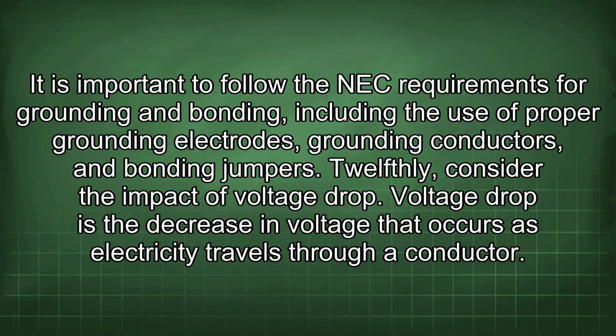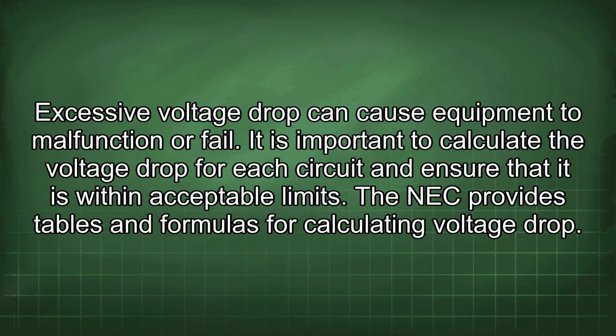12thly, consider the impact of voltage drop. Voltage drop is the decrease in voltage that occurs as electricity travels through a conductor. Excessive voltage drop can cause equipment to malfunction or fail. It is important to calculate the voltage drop for each circuit and ensure that it is within acceptable limits. The NEC provides tables and formulas for calculating voltage drop.